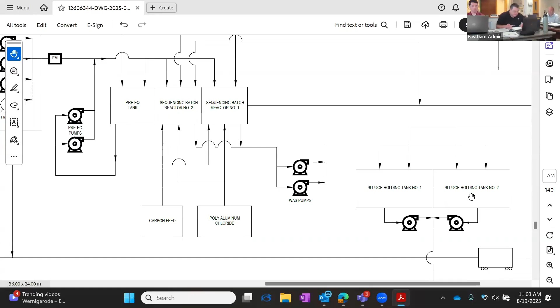So the SBR basins, the base of the design is an Aqua Aerobics 4-cycle per day SBR. I've had great luck with them as far as nutrient removal and nitrogen reduction. One I put in a few years ago in Pennsylvania, we routinely get total nitrogens on the order of 2. So, a very good, well-performing system. The supplemental carbon feed will help with the denitrification. The polyaluminum chloride will be used for phosphorus precipitation. We're also putting in sodium hydroxide for alkalinity supplementation now. By far the largest use of chemicals, that's why we got a 6,000 gallon bulk tank for that. Sludge from the equalization basins we waste to two sludge holding tanks. From there, the plan is to liquid haul it offsite for disposal.